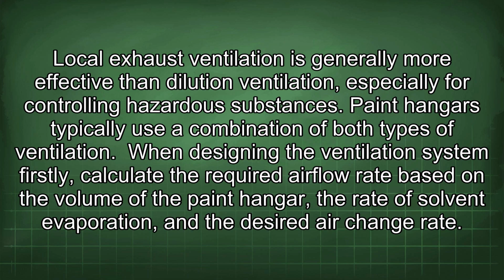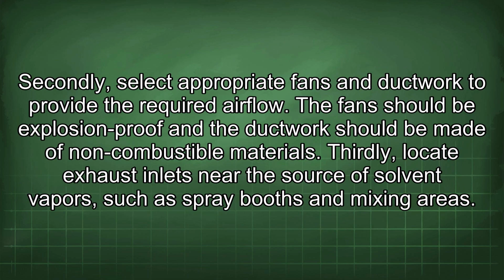Paint hangars typically use a combination of both types of ventilation. When designing the ventilation system, firstly calculate the required airflow rate based on the volume of the paint hangar, the rate of solvent evaporation, and the desired air change rate. Secondly, select appropriate fans and ductwork to provide the required airflow. The fan should be explosion-proof and the ductwork should be made of non-combustible materials.